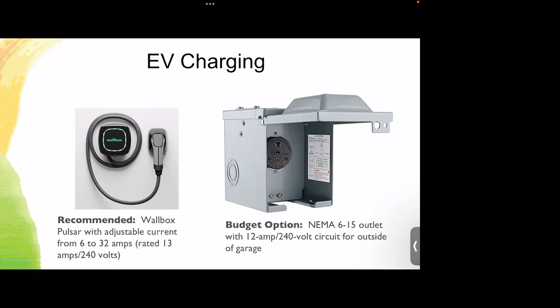One of the things we really employ in our plans is circuit pausing and circuit sharing devices. These allow you to take one, say, 240 volt circuit and share it between two devices, or pause the device if the capacity of your main panel starts to get close to its maximum. We tended to not use circuit sharing as much as circuit pausing devices, and we generally put those on the EV circuit.